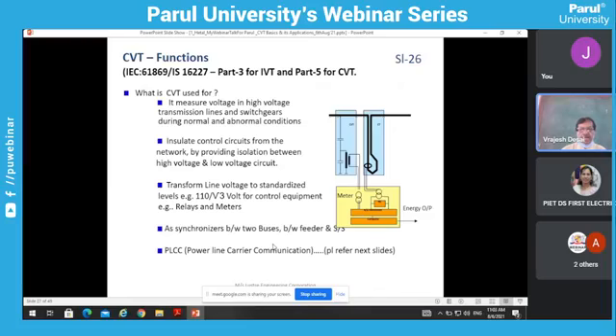As we already discussed, it measures the voltage of transmission lines and switchgear during normal and abnormal conditions. It also insulates the control circuit, which is at a low voltage, from the high voltage network. So this is isolation through insulation, that is, through capacitor banks, and the output voltage we are seeing through the voltage transformer is 110 over root 3 volts.